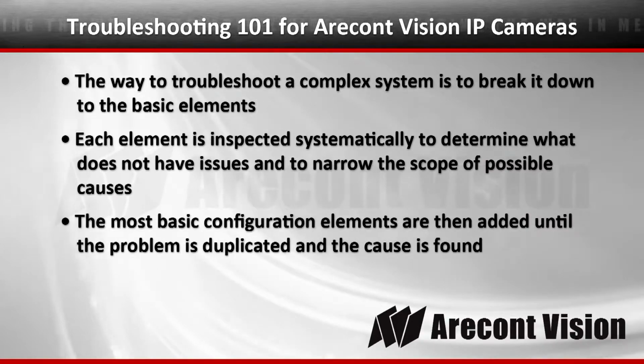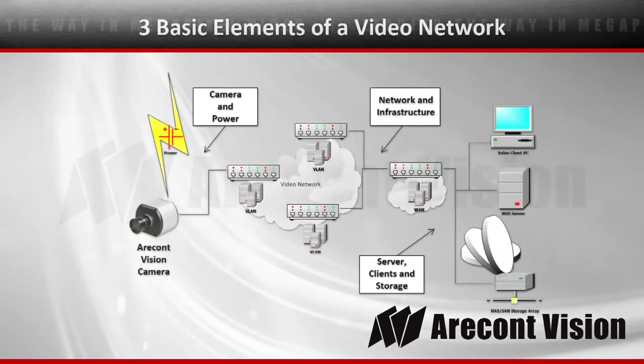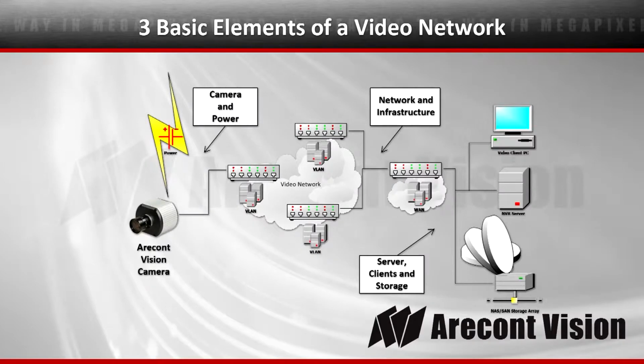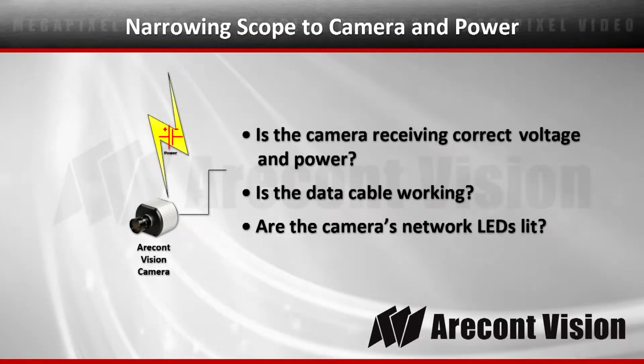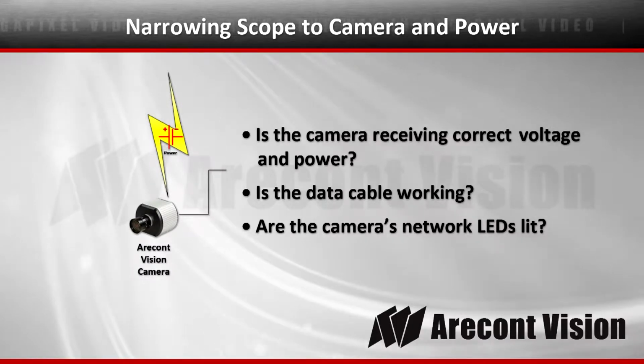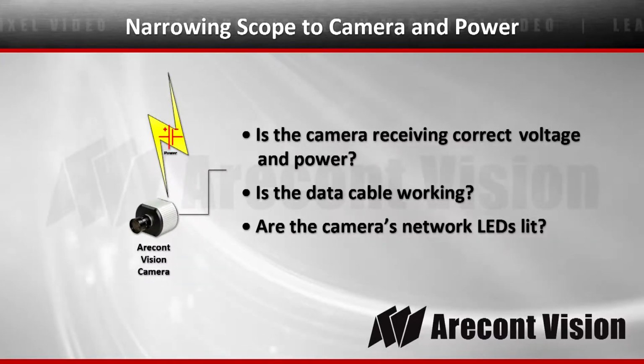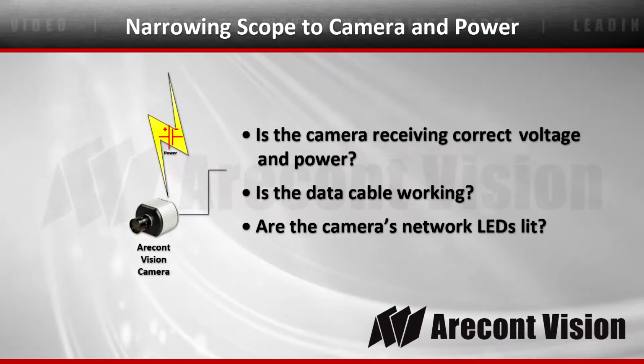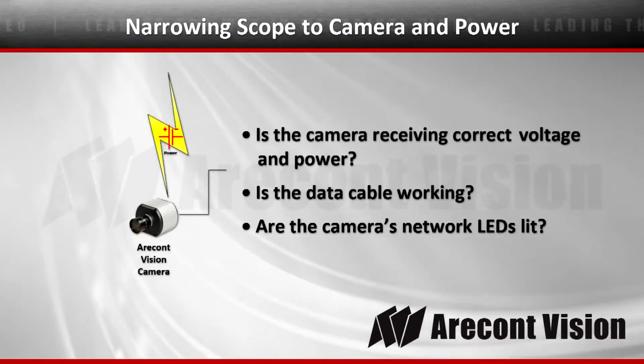For the purpose of basic troubleshooting, we're really only concerned with the power and the camera. We're going to narrow the scope to camera and power and confirm: is the camera receiving correct voltage and power, is the data cable working, and are the camera's network LEDs lit?